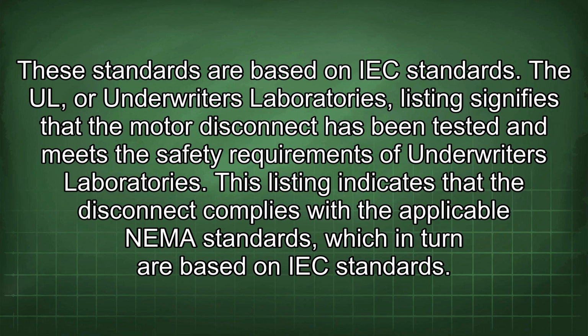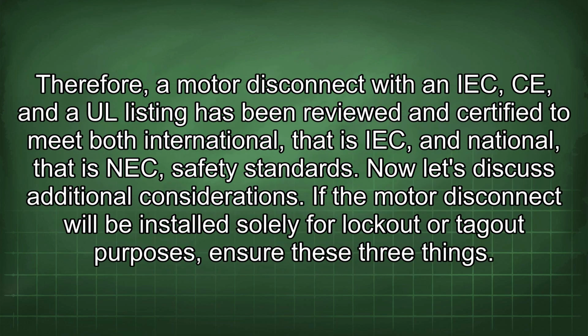The UL, or Underwriters Laboratories, listing signifies that the motor disconnect has been tested and meets the safety requirements of Underwriters Laboratories. This listing indicates that the disconnect complies with the applicable NEMA standards, which in turn are based on IEC standards. Therefore, a motor disconnect with an IEC and a UL listing has been reviewed and certified to meet both international, that is IEC, and national, that is NEC, safety standards.